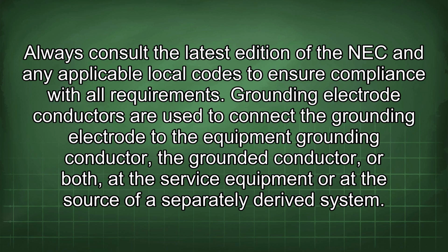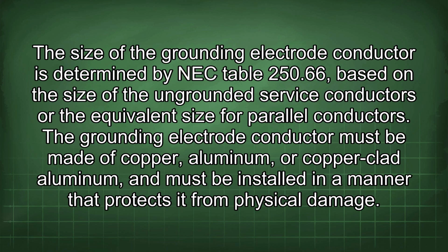Grounding electrode conductors are used to connect the grounding electrode to the equipment grounding conductor, the grounded conductor, or both, at the service equipment or at the source of a separately derived system. The size of the grounding electrode conductor is determined by NEC Table 250.66, based on the size of the ungrounded service conductors or the equivalent size for parallel conductors. The grounding electrode conductor must be made of copper, aluminum, or copper-clad aluminum, and must be installed in a manner that protects it from physical damage.